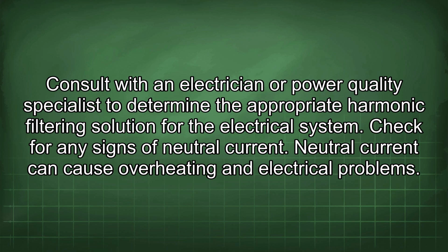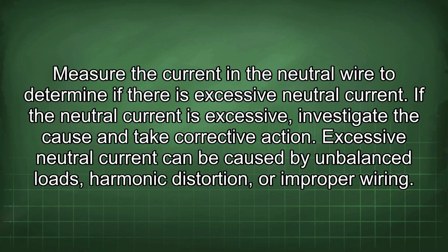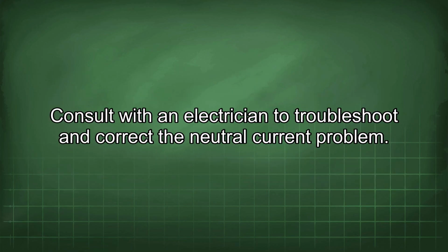Check for any signs of neutral current. Neutral current can cause overheating and electrical problems. Measure the current in the neutral wire to determine if there is excessive neutral current. If the neutral current is excessive, investigate the cause and take corrective action. Excessive neutral current can be caused by unbalanced loads, harmonic distortion, or improper wiring. Consult with an electrician to troubleshoot and correct the neutral current problem.